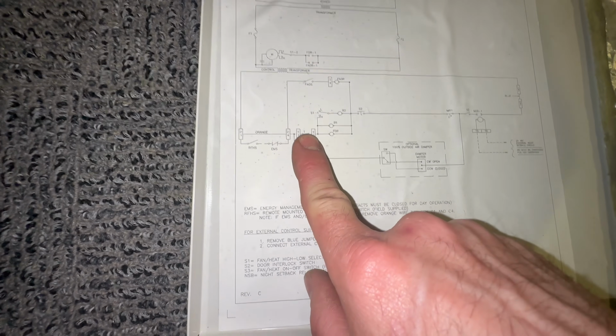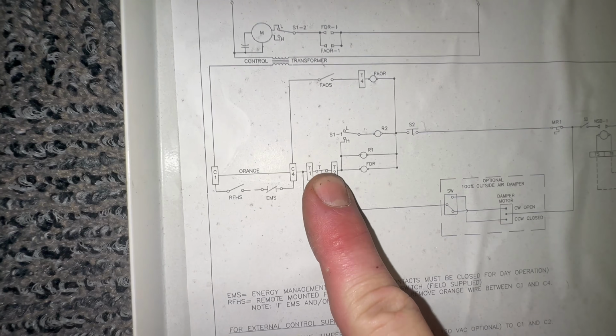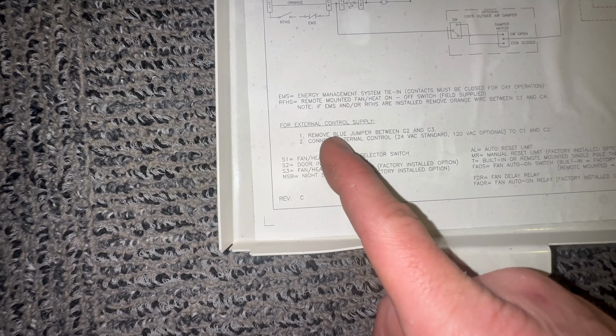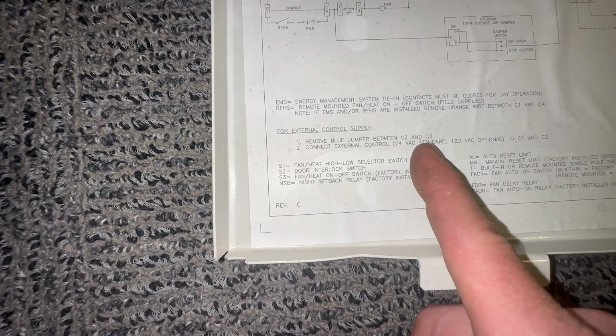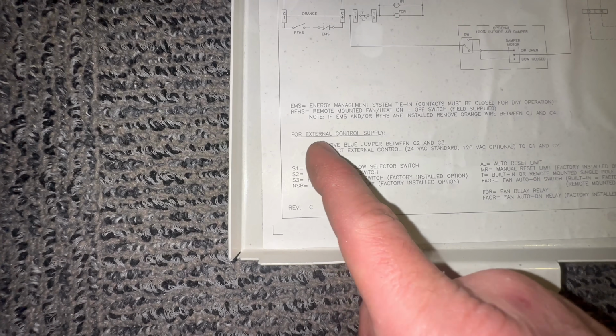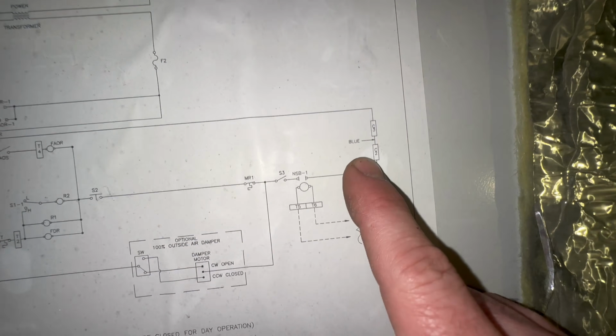Now, I just help out this property. I don't run this show, but I could tie these wires together, the thermostat, which would bypass that bad thermostat. And down here it says, remove blue jumper between C2 and C3. And this is for external control supply. So I could just put a regular battery operated thermostat up there. Go to this blue wire on this diagram.